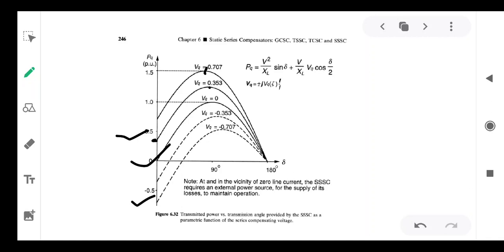But how you control the maximum peak differs between variable impedance type and converter based type. In the converter case, VQ can be controlled, and based on VQ the power flow equation changes: V square by X sin delta plus V by XL into VQ cos delta by 2. This term changes, affecting the power flow of SSSC to a great extent, making it more advantageous than the previous one.